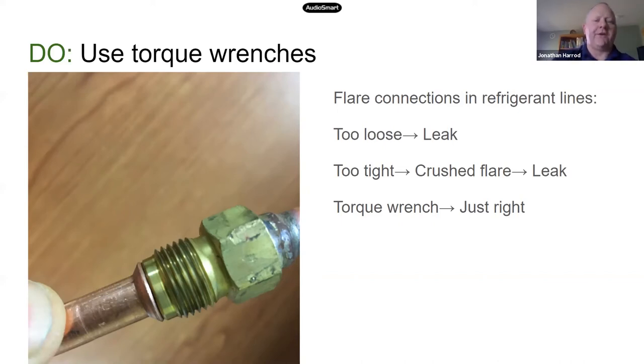And to do that, we really need to focus on flaring technique. A flare is the way that we attach refrigerant lines in heat pump systems for the most part. There's a few other options, but flaring is the dominant technique. So what we have here is a little cone of copper that we forged with a tool. It presses onto a brass cone, and then a flare nut slides over the whole assembly and tightens it down, forming a mechanical seal between the copper and the brass cone. If that nut is not tightened enough, we get a leak. If it's tightened too much, it'll actually crush this flare and we'll get a leak. So we have to get that just right. And the only way to get the torque on these flare nuts just right is to use a torque wrench.